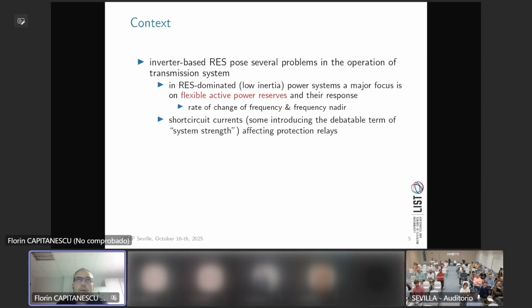Obviously we may face frequency issues, like rate of change, where the frequency after a contingency could drop very fast or drop very low. So it's rate of change of frequency, nadir of frequency, and so on. There are plenty of works on this, but there are also simple technological solutions to deal with that, like installing plenty of synchronous condensers in your system, if you have enough space in substations.